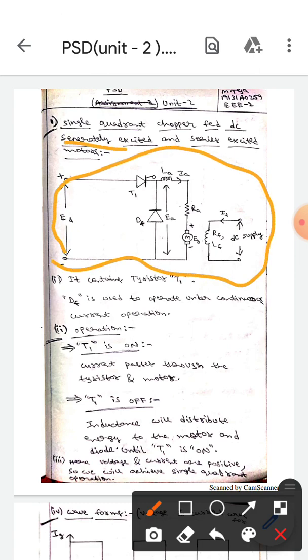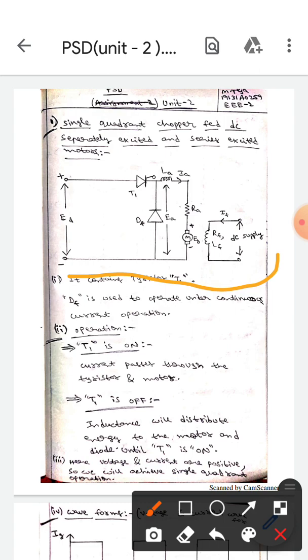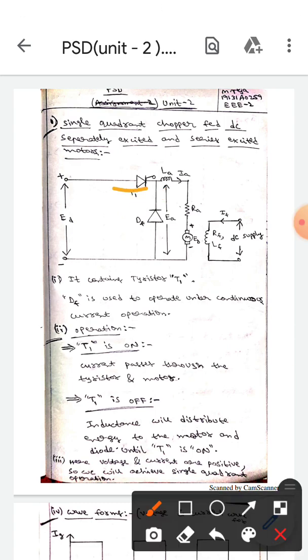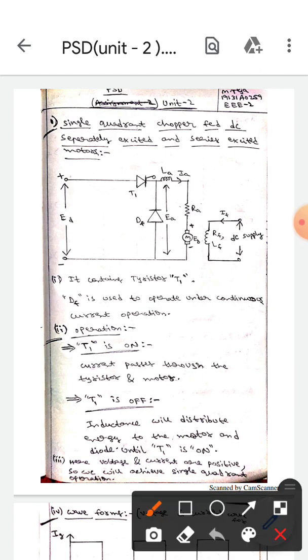The circuit contains a thyristor T1, and DF is the freewheeling diode used under continuous current operation. When T1 is on, the current will pass through the thyristor and motor. When T1 is off, the inductance will distribute energy to the motor and diode until T1 is on again. Here voltage and current are positive, so we achieve single quadrant operation.